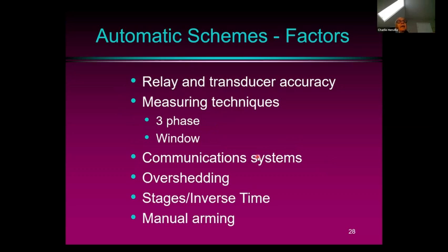Some of the things that would be needed, for instance, are very accurate relays and transducers, because as we saw, the voltage collapse point happens very close to normal or required voltage levels. So you need very precise measurement of voltages before you take any, I nearly said catastrophic, but I should have said extreme action to shed firm load. So if you're measuring voltage, you'd always use three-phase voltages and make sure voltages were low on all three phases. And you need a window so you can be sure that the voltage just didn't disappear because you switched the voltage measuring device offline. As I showed you in that scheme earlier, you need communication systems because you'll be measuring the voltages at different locations.